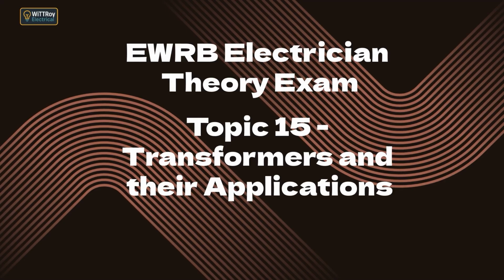15.1 General. 15.1a. Explain the principles of operation for the double wound transformer and the auto transformer. A double wound transformer has two separate windings, a primary and a secondary, wrapped around an iron core. When AC flows in the primary, it creates a changing magnetic field. This magnetic field induces a voltage into the secondary. There is no electrical connection between the two windings, only magnetic coupling, and this provides electrical isolation.